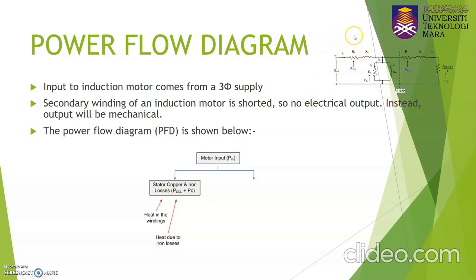which is the stator winding resistance. The PC, the core losses, is due to RC, which is the stator core loss resistance. So the PC losses happen here, and the stator copper losses happen here.